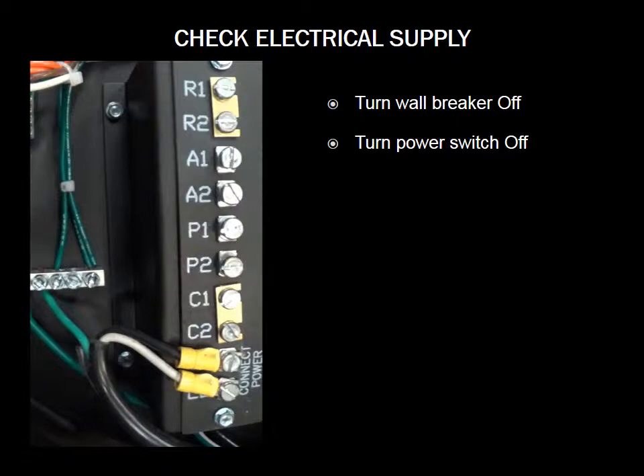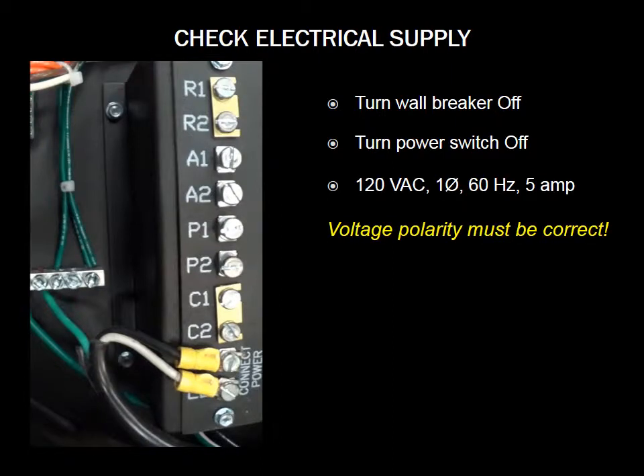Begin by making sure the wall breaker is off and the unit's power switch is turned to the off position. Next, check the electrical power supply to the unit. The water heater requires a 120 volt, single phase, 60 Hz, 5 amp power supply and must also be electrically grounded. Now check to make sure the wiring is correct on the field access terminal board at the top of the unit.